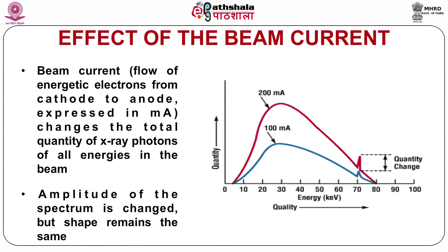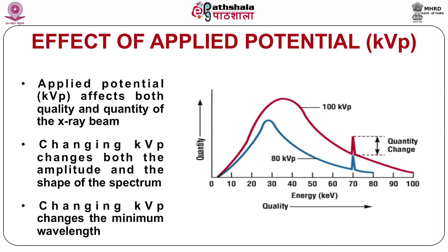Applied potential affects both quality and quantity of the X-ray beam. Changing the kVp changes both the amplitude and the shape of the X-ray spectrum. In addition, changing the kVp also changes the minimum wavelength of the X-ray beam. This has been shown in the figure. The figure shows the X-ray spectrum for the X-ray tube operated at two different energies, one at 80 kVp and another at 100 kVp. So now we see here that changing kVp changes both the amplitude and the shape of the spectrum. Changing kVp changes the minimum wavelength as well.